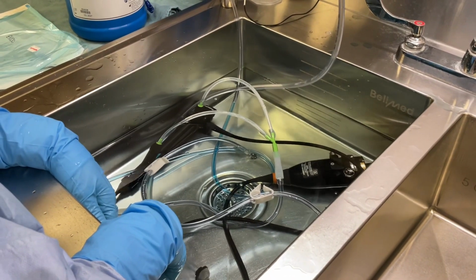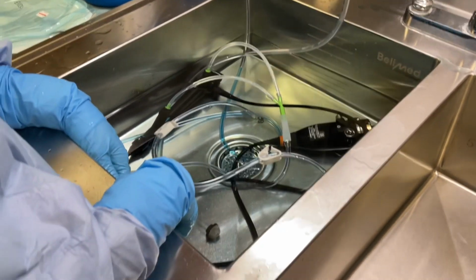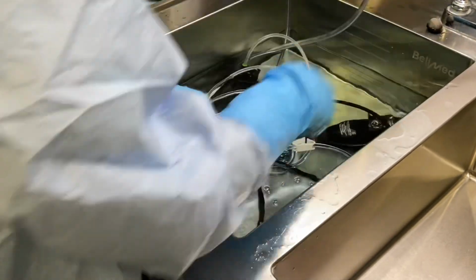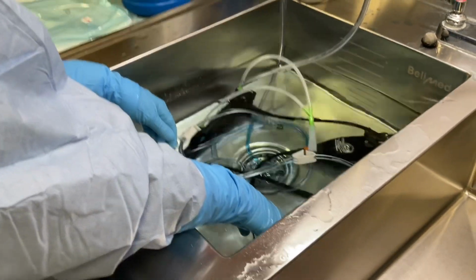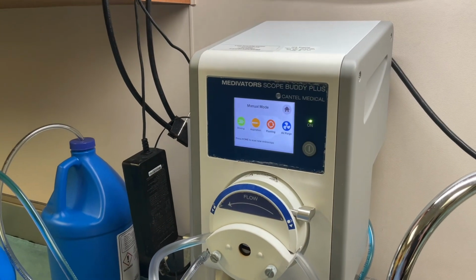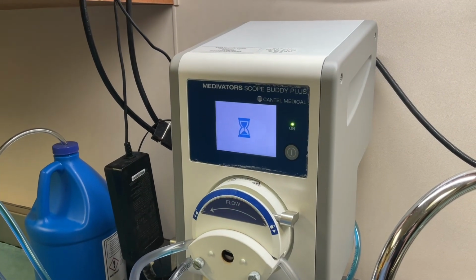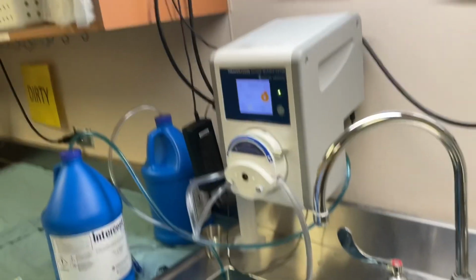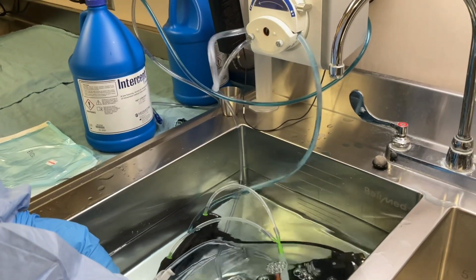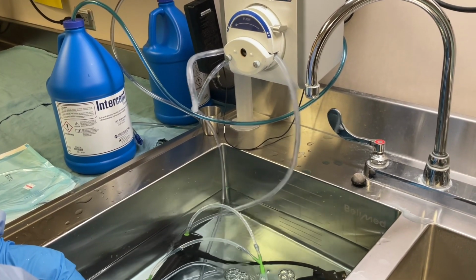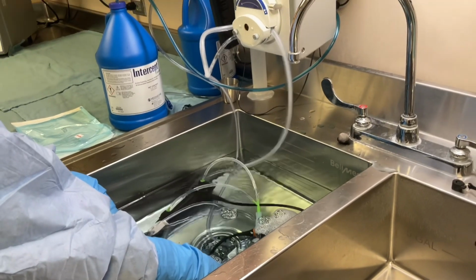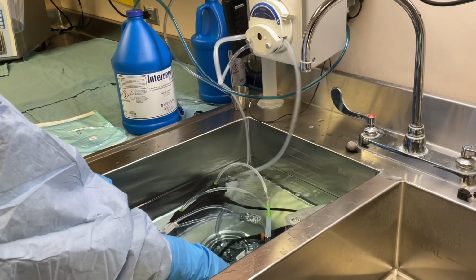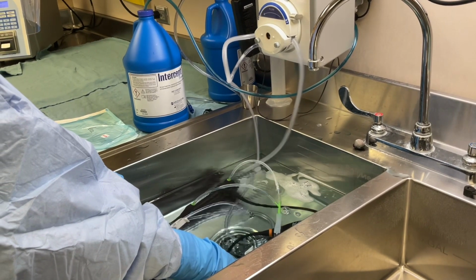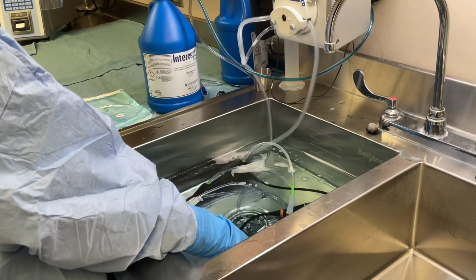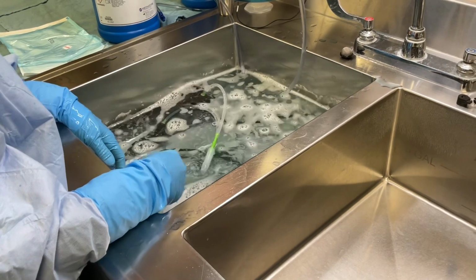Completely immerse the endoscope in detergent solution. Remove the strainer from the end of the pump tube and place it on the counter. Position the end of the pump tube without the strainer over the sink. Press play to aspirate detergent through the instrument and suction channels for 30 seconds. Make sure to soak the endoscope for 1 minute. This is the detergent contact time.